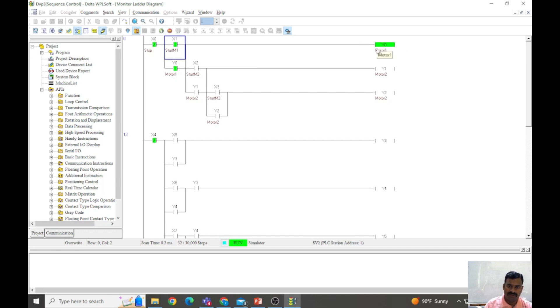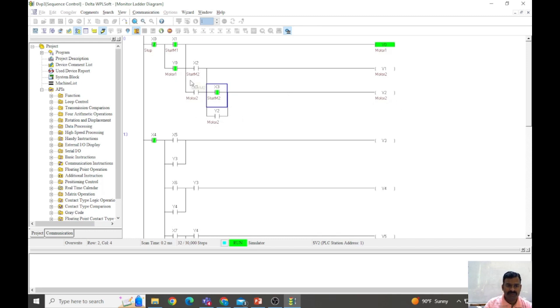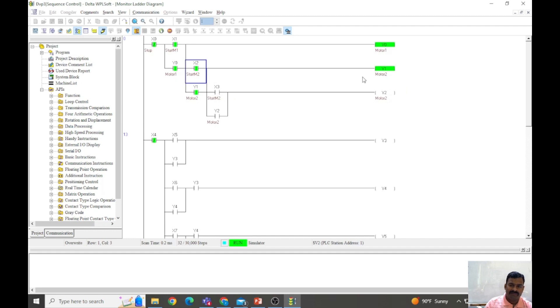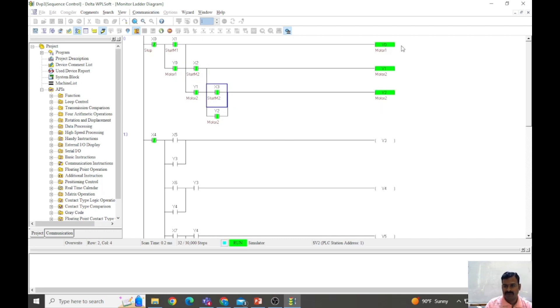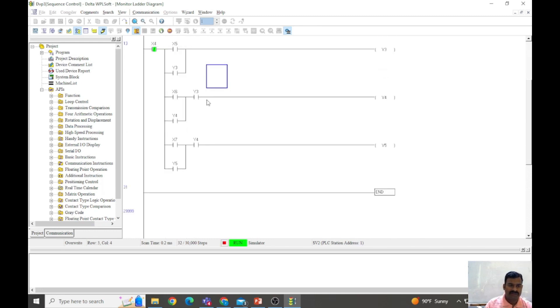If I don't follow the sequence and go directly to X3 to start Y2, let us see what happens — I turned on this switch but since we don't have power from the previous stage, motor number two is not getting energized. So let us go back to the normal sequence. Let me start the second motor by operating X2 — now X2 is pressed and Y1 the second motor is connected. Now I operate X3 so the third motor turns on. This is the sequence: Y0, Y1, Y2. If you don't follow the sequence, the machines will not turn on.